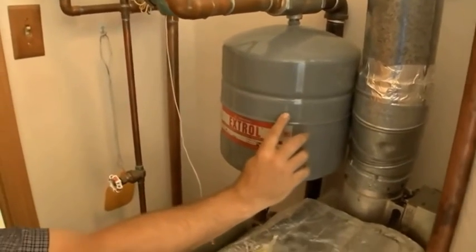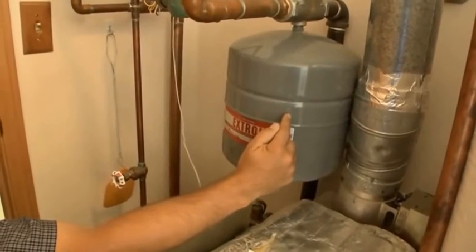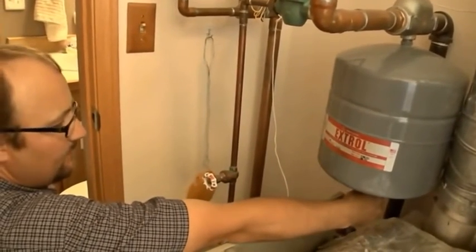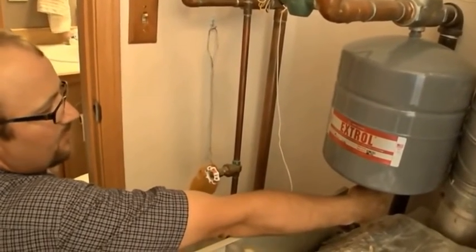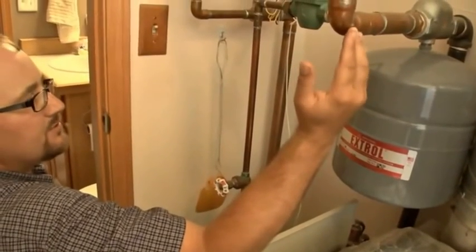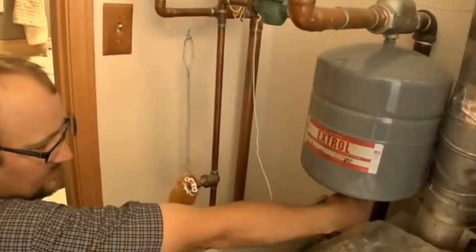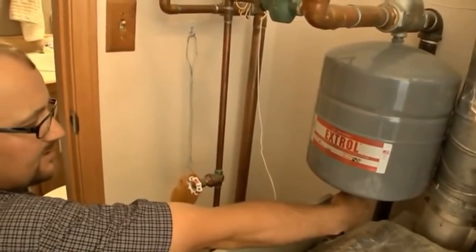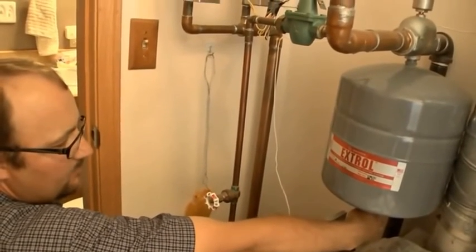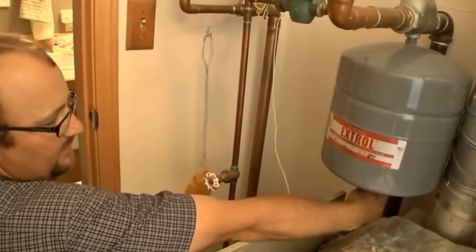The other trick is you cannot check the pressure on these reliably when the system is pressurized. You need to check it when it's not pressurized. So in order for me to set the pressure for this, I need to relieve the pressure on the boiler, get it down to 0. I take just like a tire gauge, put it on here, and I check my pressure. If I'm below 12 psi, then I add a little bit of air to get it to 12 psi, and vice versa. If I'm above, I let a little air out.